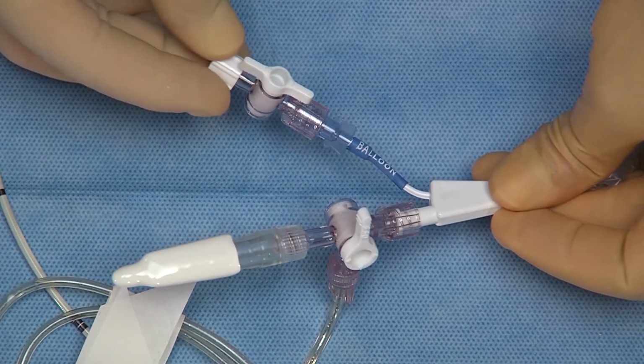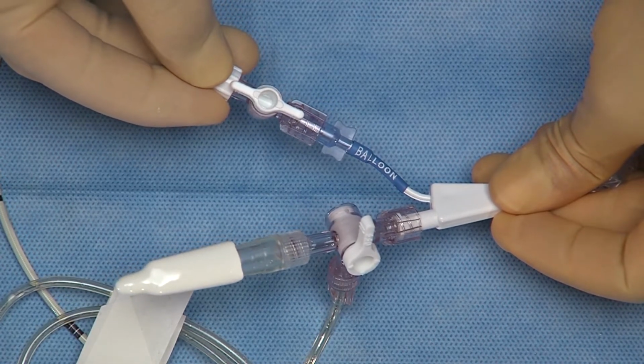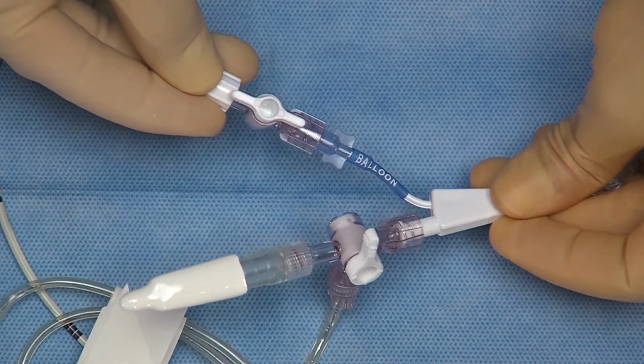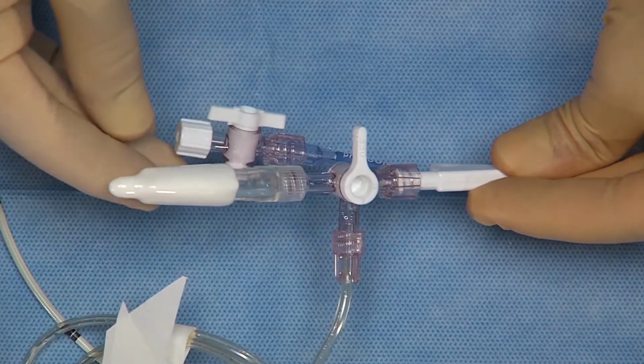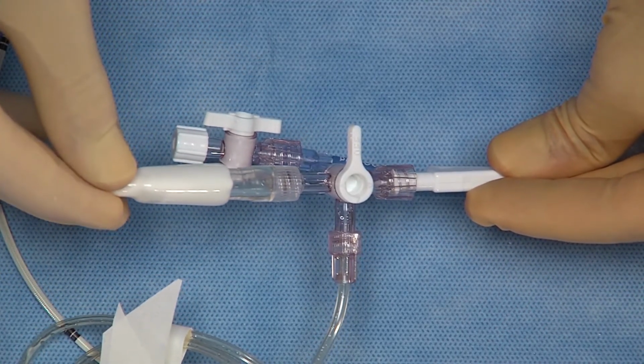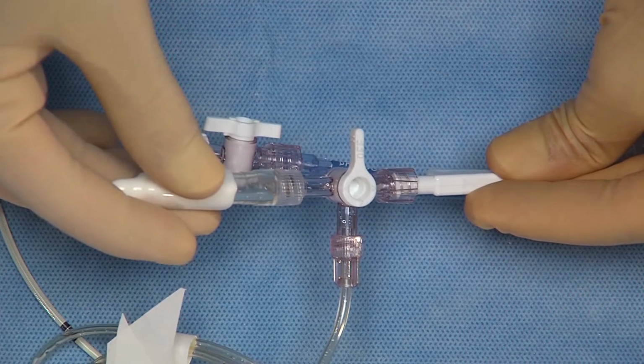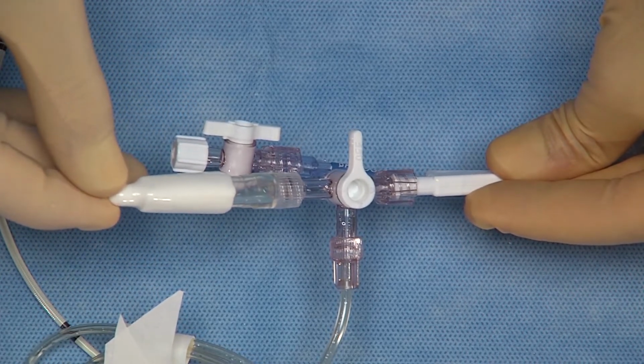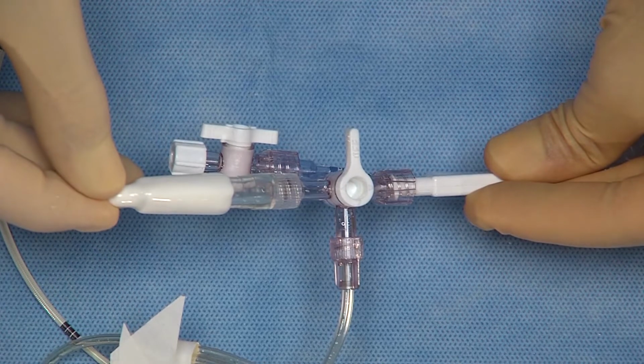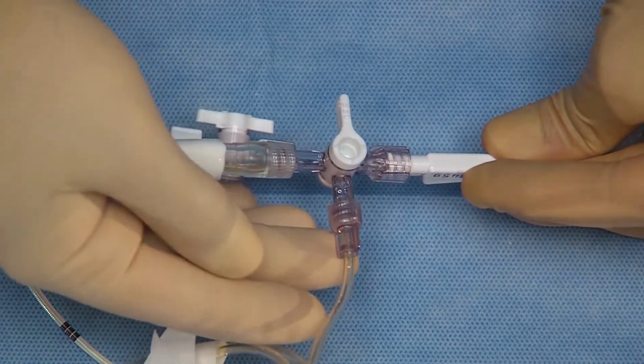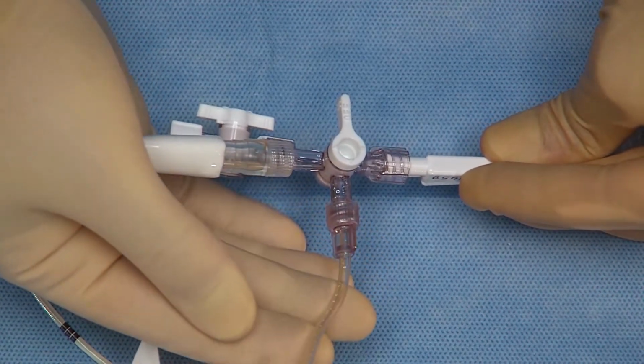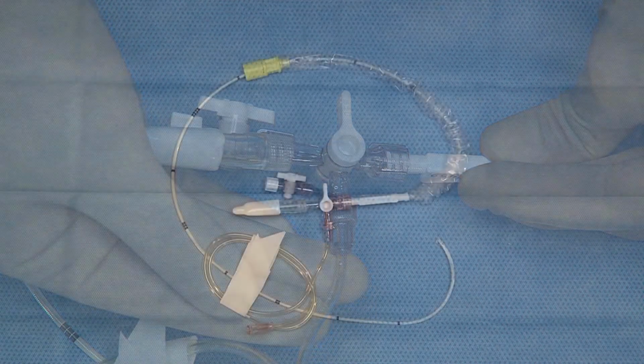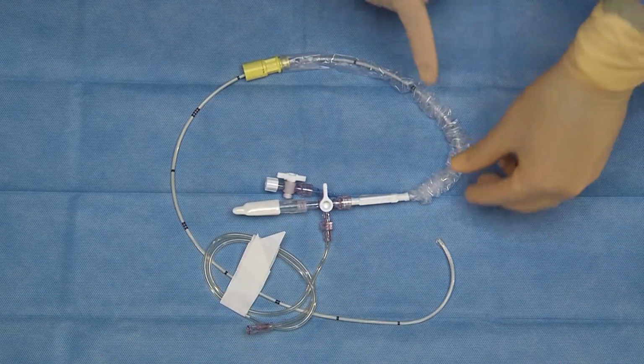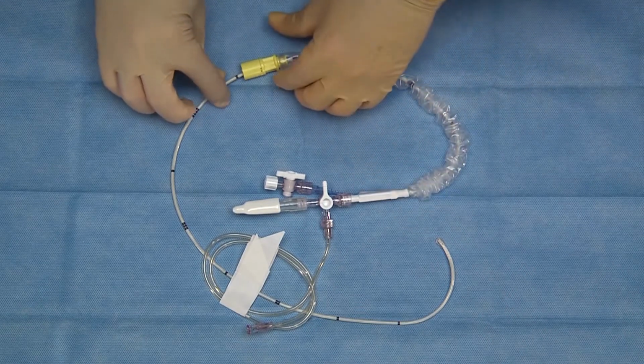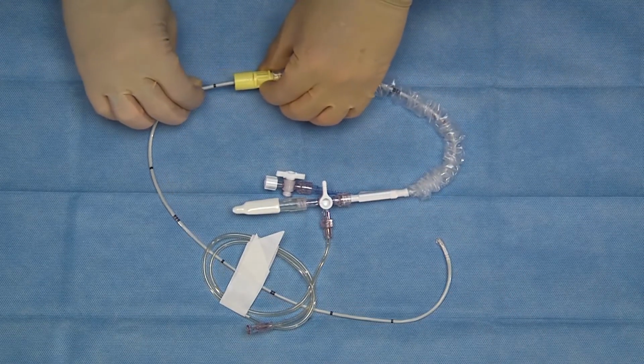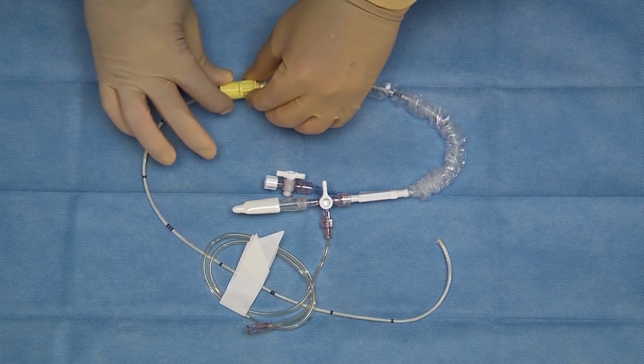The two-way stopcock is attached to the balloon inflation and deflation lumen. The three-way stopcock has attachments on each of the two ports. A hose barb adapter is attached to the end port to enable the connection of the pulmonary artery venting line. A pressure line is attached to the side port to allow for the monitoring of pulmonary artery pressure. The device is protected by a contamination guard, which will protect the catheter shaft and be positioned when the clinician attaches it to the introducer.